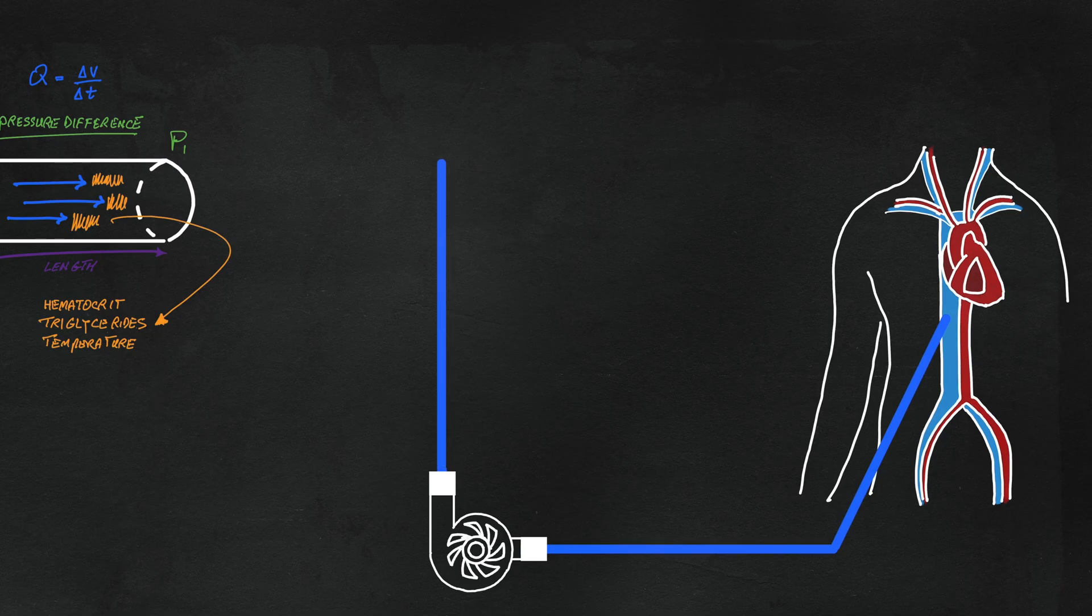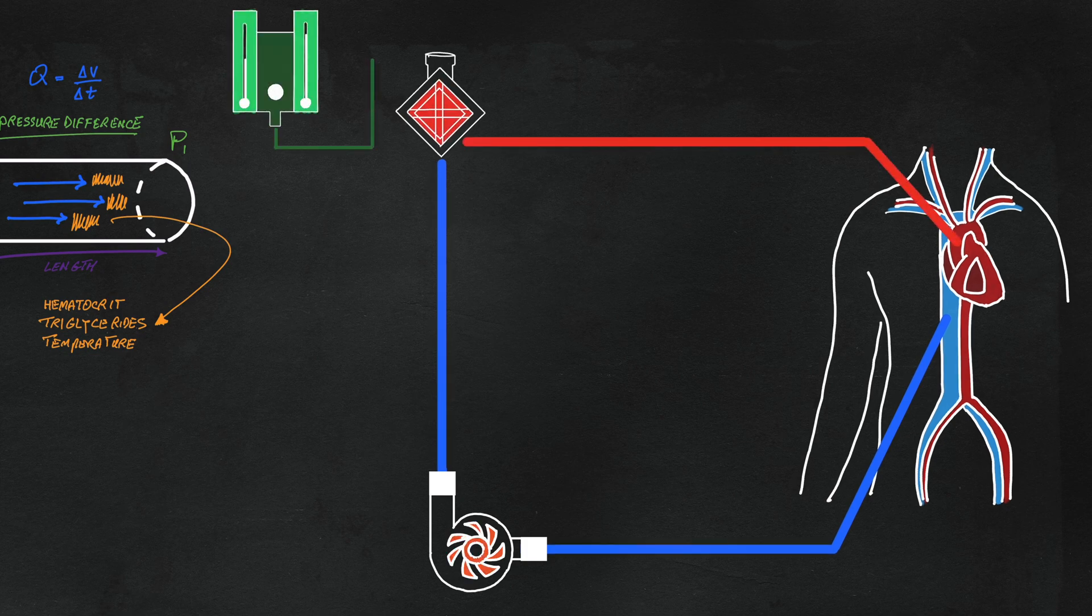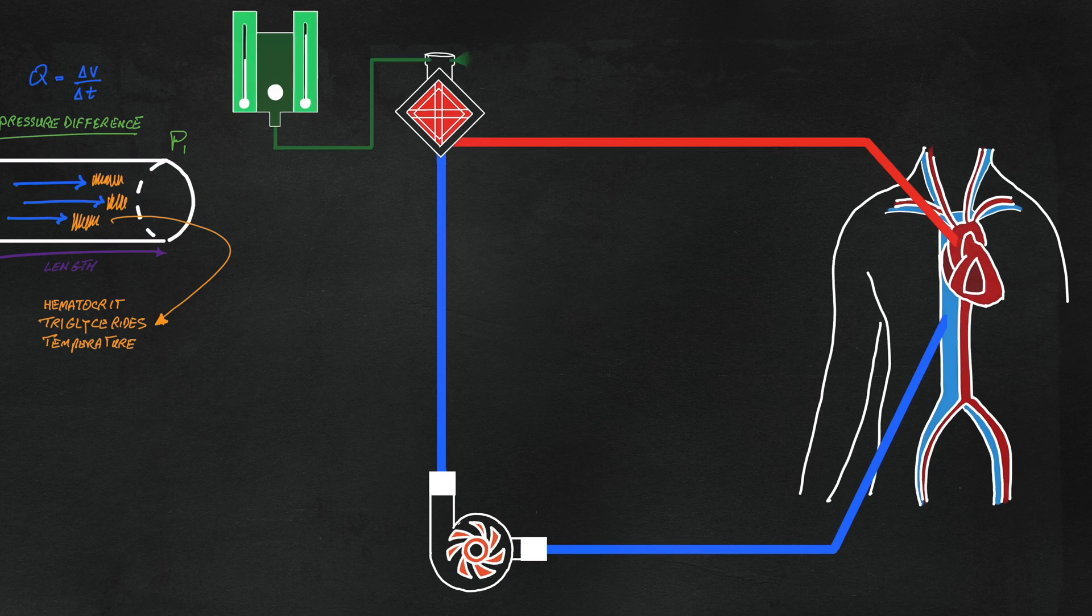Basic ECMO configuration consists of a pump, membrane oxygenator, tubing, vascular access, and cannulae. The oxygenator is connected to a source of fresh gas flow via an air-oxygen blender and heat exchanger.